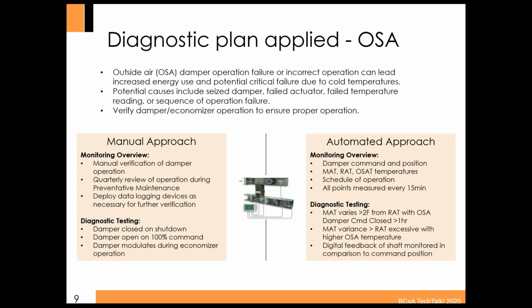Or maybe it's more frequent and you're seeing a high failure rate of your outside air dampers, and you're shifting to more of a monthly review. And even with the pneumatic system, there's quite a bit of capability to deploy data logging devices, HOBOs or others, in order to get additional data collection on the temperatures and the performance of that system over time. But that in-the-field check, looking at it from a diagnostic standpoint, is reviewing that the damper is closed when the system is shut down or when it's commanded closed.